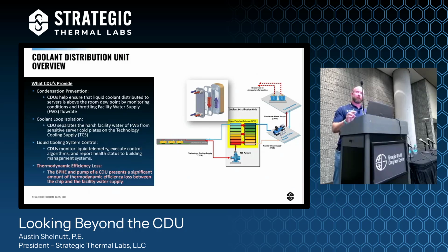But we can't ignore the thermodynamic efficiency loss imposed by the CDU. At best, it's a thermodynamic parasite in the overall system of removing heat from processors and sending it to the outside air. That's the way that I view it. I think many people view it as a necessary evil, and in many cases it is a necessary evil. That doesn't mean that we shouldn't try to solve that problem.